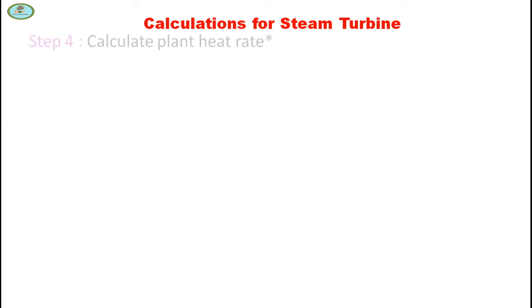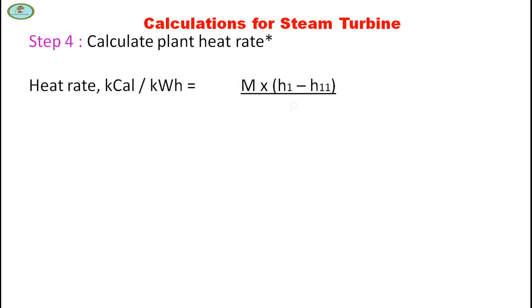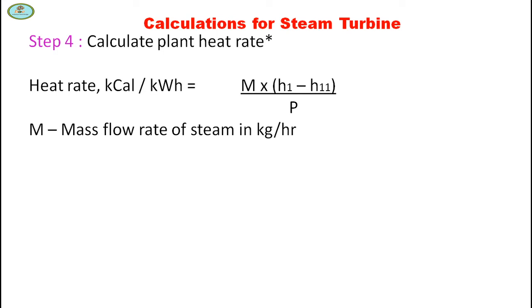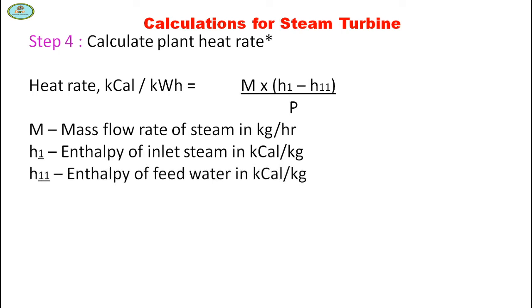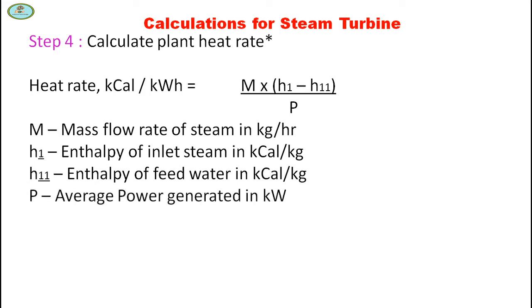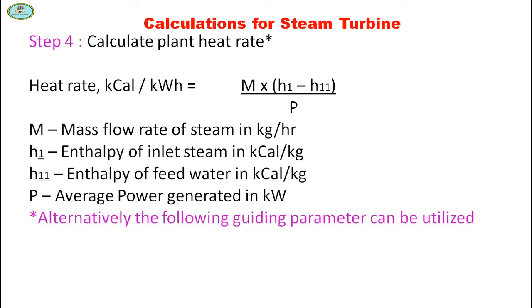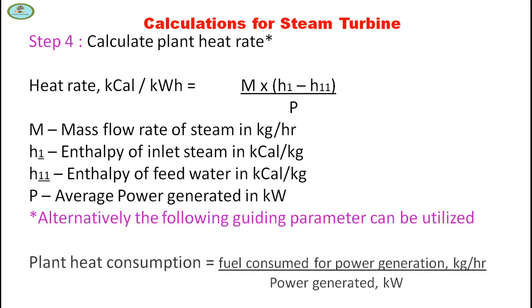In Step 4, calculate plant heat rate. Plant heat rate equals M times (H1 minus H11) divided by P, where M is mass flow rate of steam in kg/hr, H1 is enthalpy of inlet steam in kcal/kg, H11 is enthalpy of feed water in kcal/kg, and P is average power generation in kilowatts. Alternatively, plant heat consumption equals fuel consumed for plant generation in kg/hr divided by power generated in kilowatts.